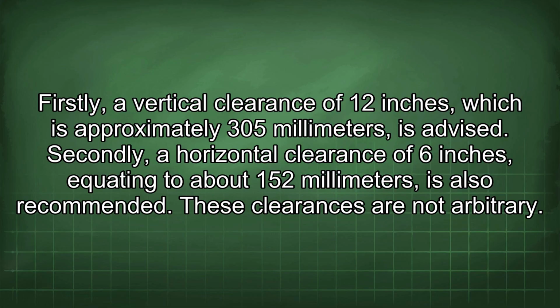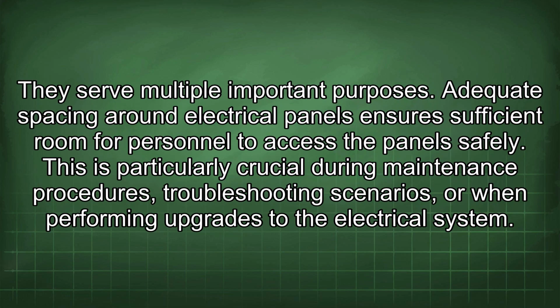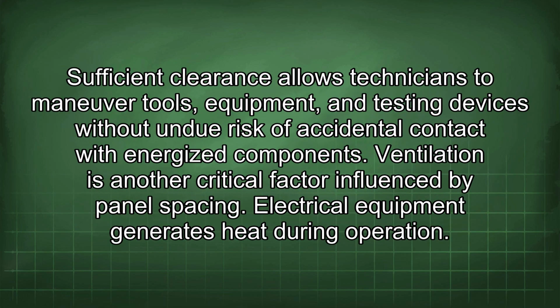These clearances are not arbitrary. They serve multiple important purposes. Adequate spacing around electrical panels ensures sufficient room for personnel to access the panel safely. This is particularly crucial during maintenance procedures, troubleshooting scenarios, or when performing upgrades to the electrical system. Sufficient clearance allows technicians to maneuver tools, equipment, and testing devices without undue risk of accidental contact with energized components.